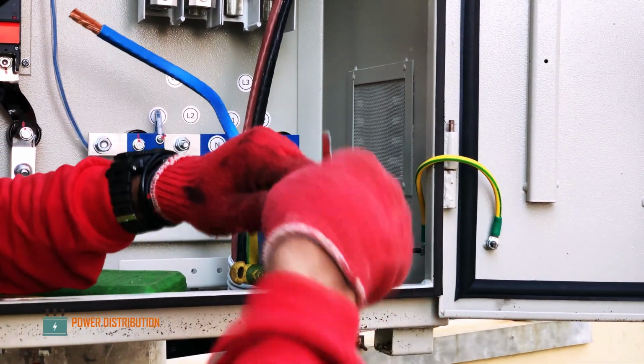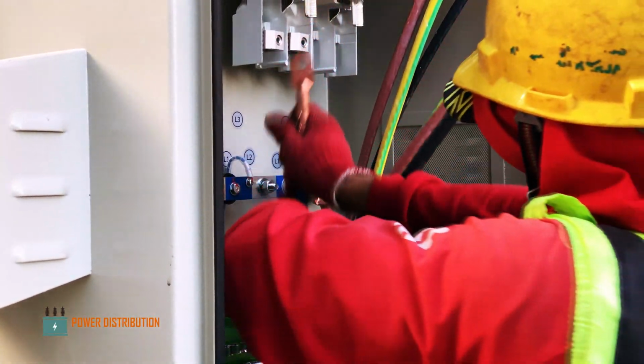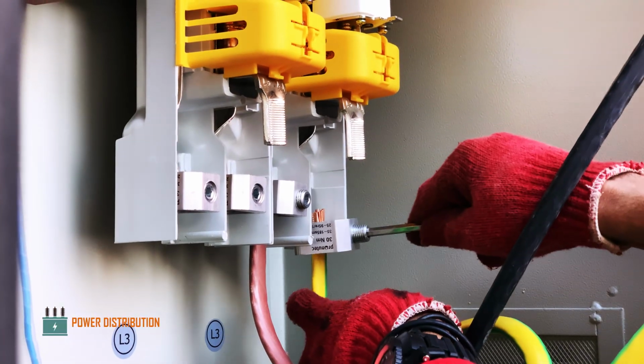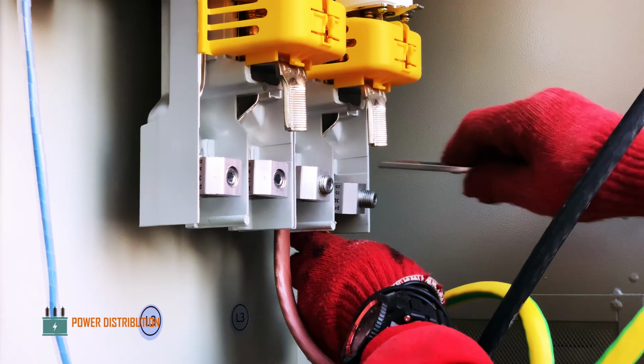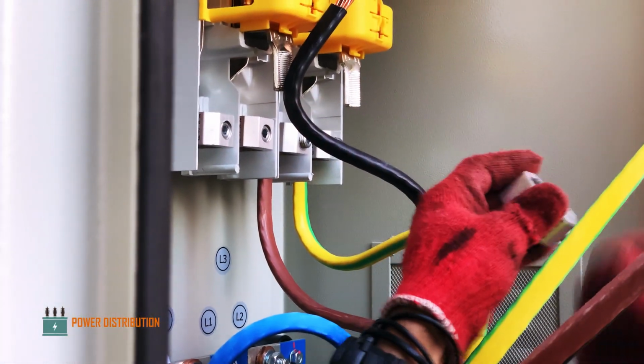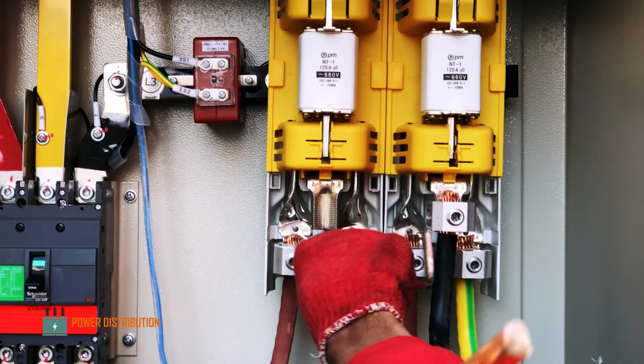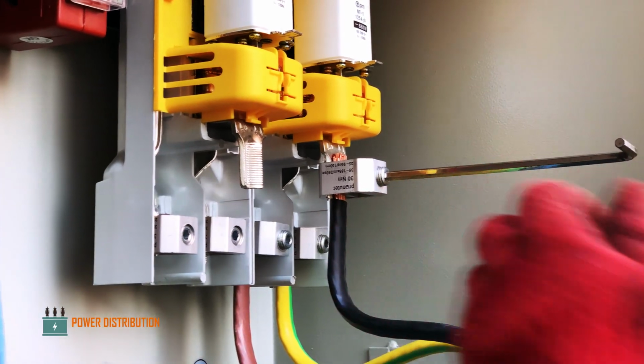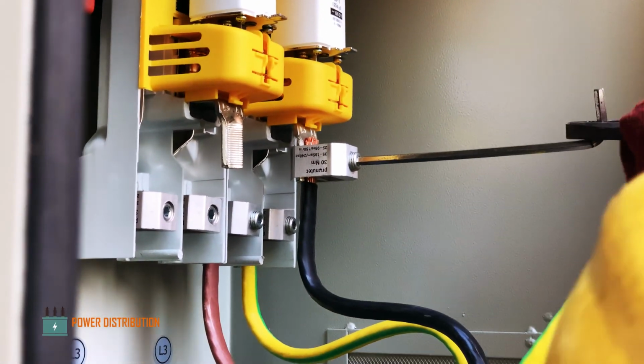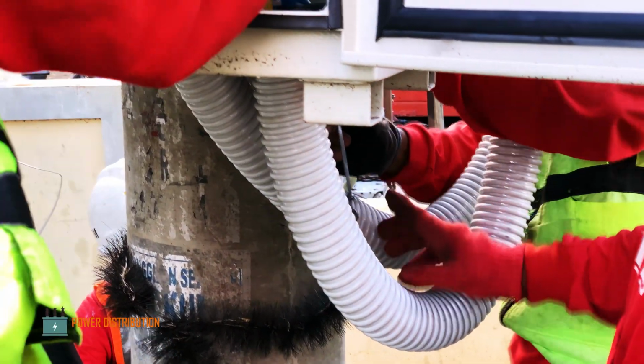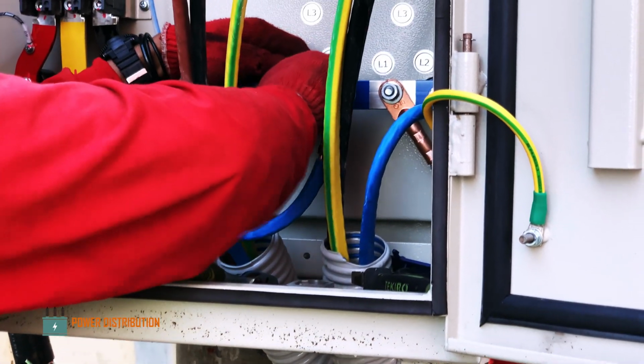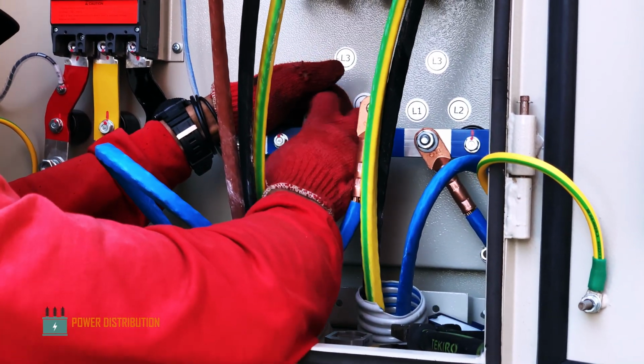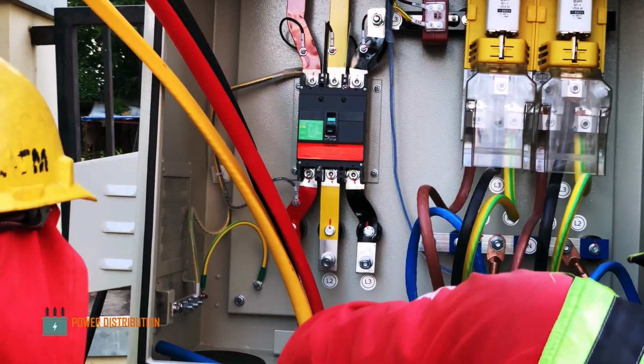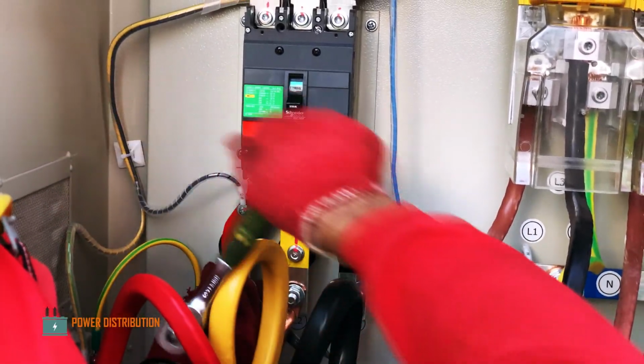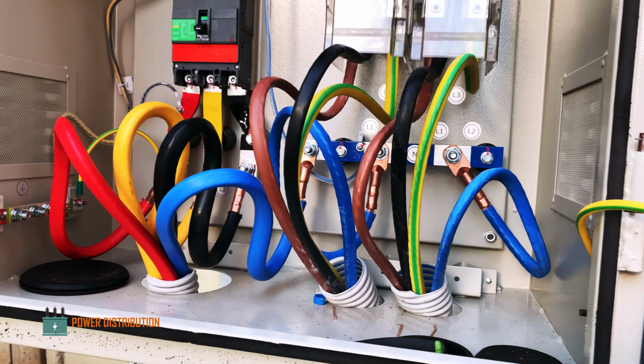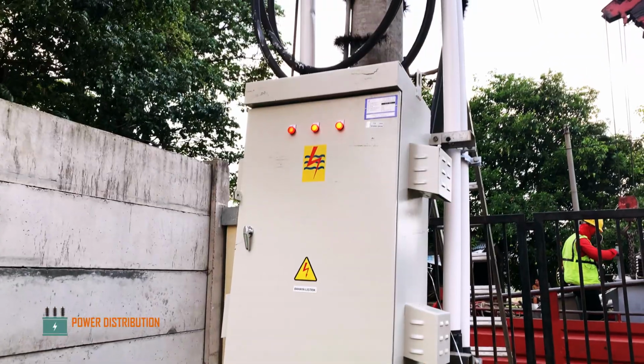The ground crew pulls the conductor cable and then attach the distribution buses for each phases and secure the wire in place using a metal clamp. And then attach all the neutral wire to the same neutral bus. And last but not least, they install the main power cable into the NFB or the main breaker. Now all the connection is completed and ready to be energized.